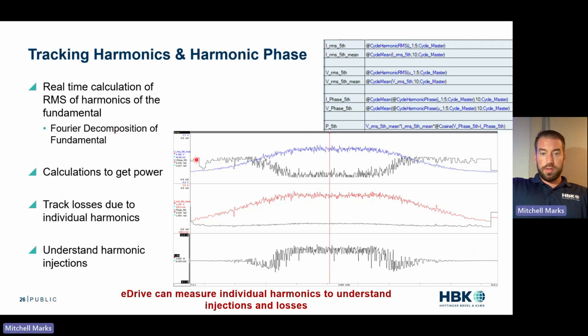So what I show in this graph here is, on that dynamic basis, on that cycle basis, we are looking and saying, okay, here's my amplitude of my fifth harmonic voltage in blue. Here's my phase in black. Here's my amplitude of fifth harmonic current in red, on the cycle basis. Here's my phase in black, and then here's my power, and it's bouncing all over. But if you have the right accuracy and you can trust this, 5 watts in your measurement uncertainty, this is an awesome measurement, and you can start to characterize your harmonic losses.